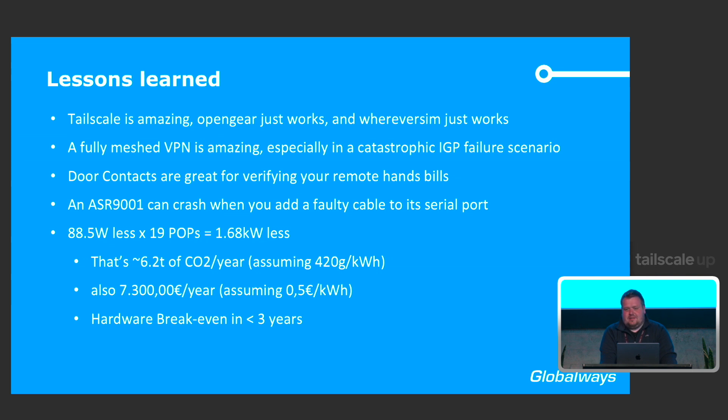Another lesson learned, and I'll be honest — we didn't plan for it. Looking at power consumption in retrospect, reducing our draw by roughly 88.5 watts times 19 POPs really adds up. It saves 6.2 metric tons of CO2 per year. And it saves quite a lot of money — roughly 7,300 euros per year — which results in a hardware break-even in less than three years. This is now something we take into account when re-evaluating hardware decisions.